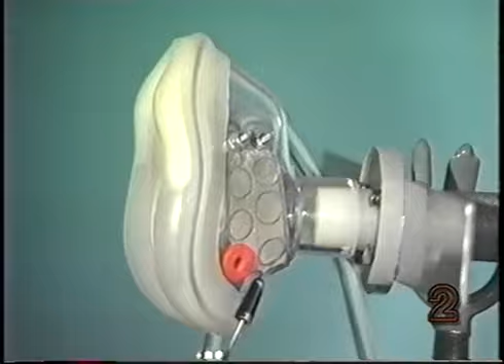Right here is a pressure tap that's also a port to the air pressure transducer, which is mounted right on the mask. This particular transducer has a wideband frequency response in that it picks up higher frequency flow components than most typical air pressure transducers. It's because of this response that it produces a waveform that looks very much like a voicing waveform. Notice that we have a second pressure tap which leads to a second transducer with a lower frequency response. It's from this transducer that we generate the average airflow and the volume waveforms.